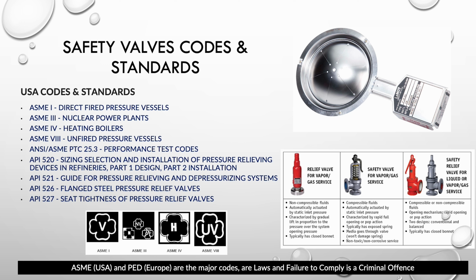In this example, when it relieved, it relieved directly into our parking lot and into the walkway where we have people progressing. Hindsight's always 20/20. That's obviously not a great design, because if it relieves while somebody's walking in the path, guess what?